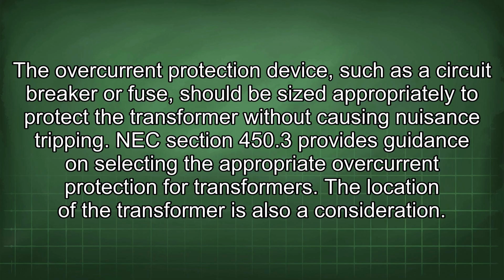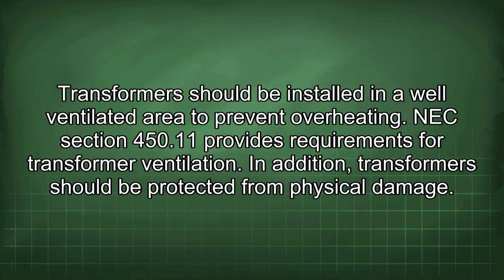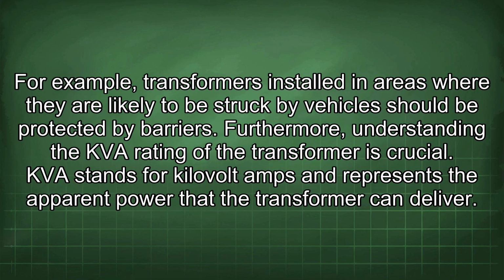The location of the transformer is also a consideration. Transformers should be installed in a well-ventilated area to prevent overheating. NEC Section 450.11 provides requirements for transformer ventilation. In addition, transformers should be protected from physical damage. For example, transformers installed in areas where they are likely to be struck by vehicles should be protected by barriers.